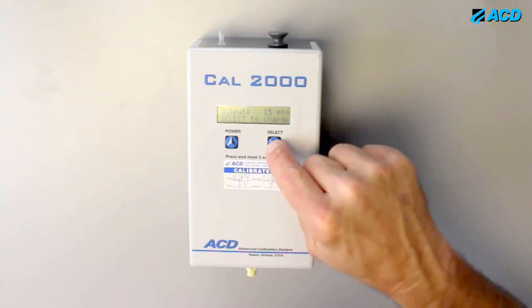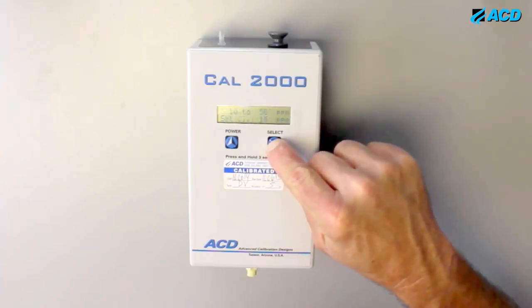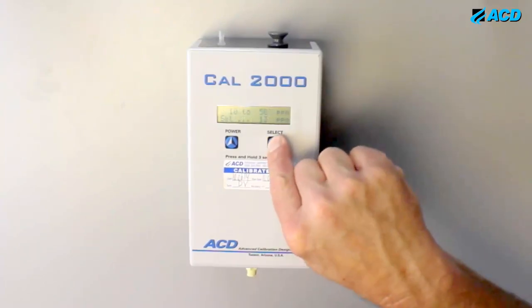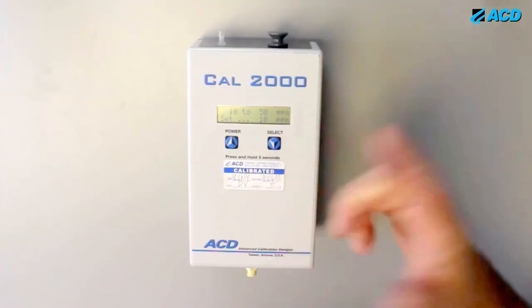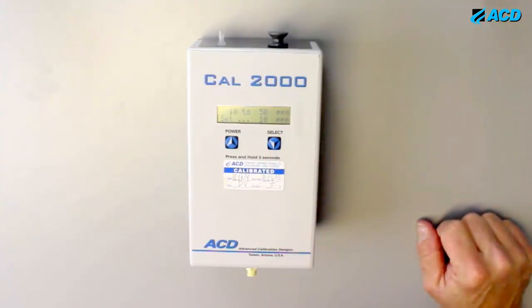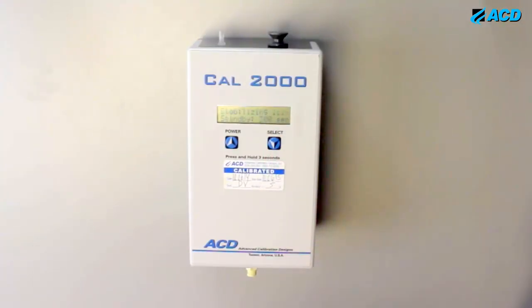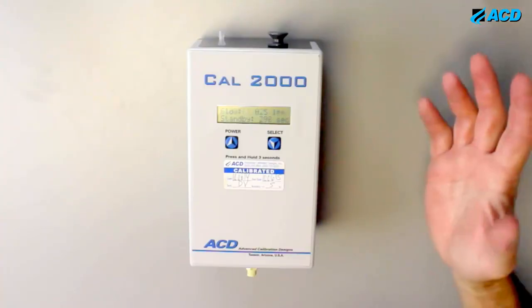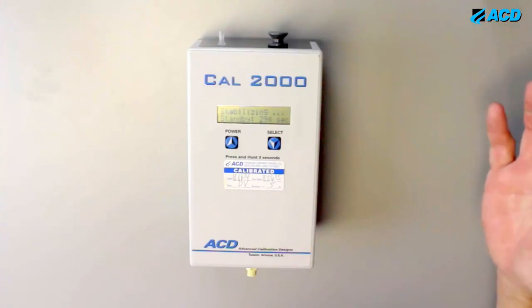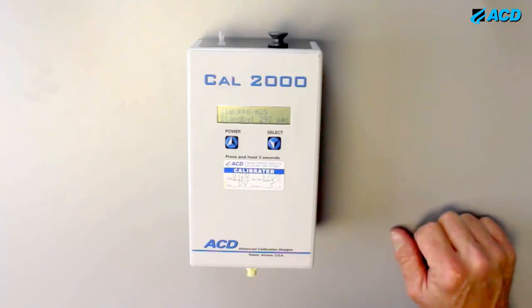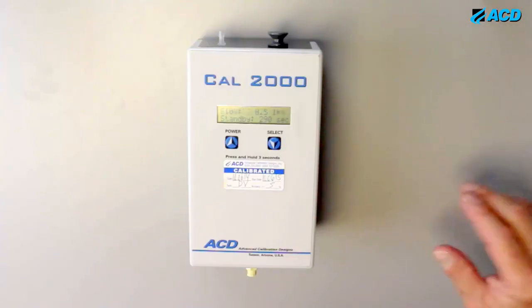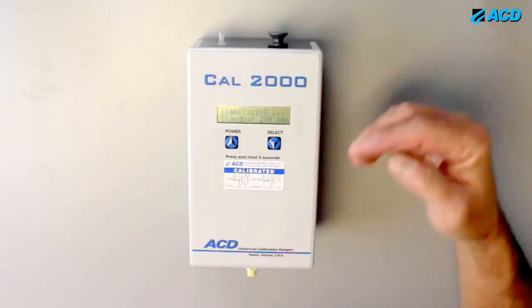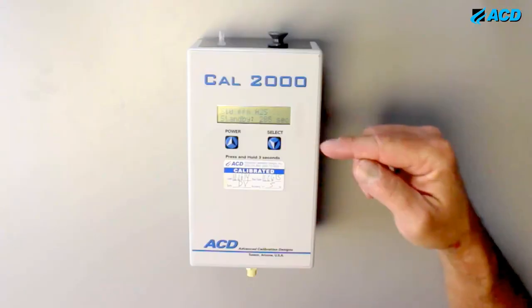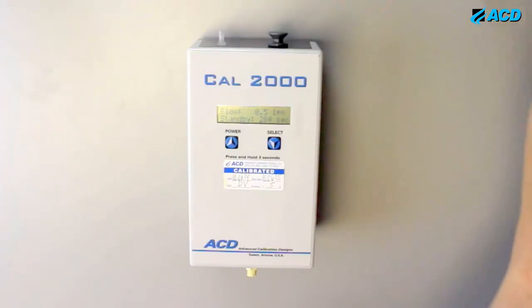Now it shows me concentration, 15 ppm, select to change. Now I can go up and down, okay? So I'm going to change it to 10 parts per million. This way you can calibrate anybody's sensor virtually on the market. Whatever concentration they ask for, you just set the unit to it and that flow rate and go, okay? So there's the unit's calibrated, it's stabilizing at 10 ppm, half a liter a minute, okay?